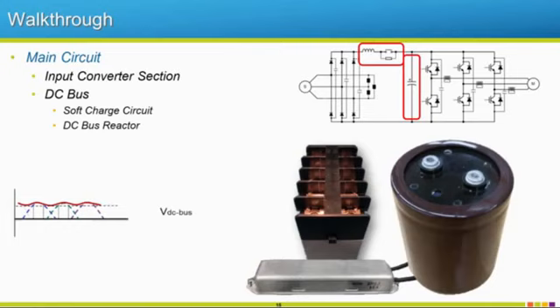Then we move to our DC bus. So we've got the top part of that waveform that we chopped in half with our diodes. And since we have this capacitor here, we're actually going to start to fill in these voids. So it's going to smooth out this DC bus ripple, which is very bad for a drive. So things that would cause excessive DC bus ripple would be like if you would try to single phase a drive. But if we have three phase incoming, you have that 120 degrees evenly distributed waveform going across here for all three phases. So it smooths out that DC bus quite a bit with the help of this capacitor.